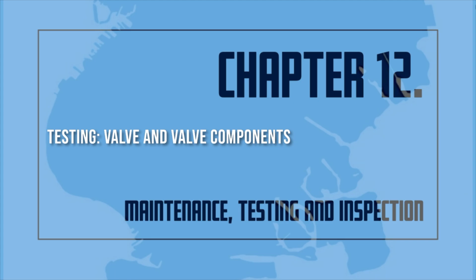A full flow trip test requires at least 2 individuals, one of whom is situated at the dry pipe valve while the other is at the inspector's test. If possible, they should be in communication with each other. A full flow trip test is conducted as follows. 1. The main drain valve is fully open to clean any accumulated scale or foreign material from the supply water piping. The main drain valve is then closed.